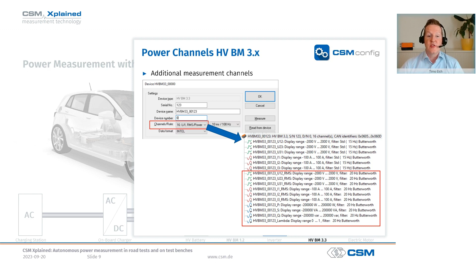And here with the AC measurement, you as a professional will already recognize that this calculation principle also comes to its limits with very specific, more demanding applications, for example, with dynamic load changes. Because then you simply need the dynamic detection of the period duration from the raw signals, as it is implemented in the Vector e-mobility analyzer, for example. The principle of the Aron circuit also partially reaches its limit due to the assumptions of the 2-wattmeter method. So no leakage current and no unbalances on the 3 phases are taken into account.